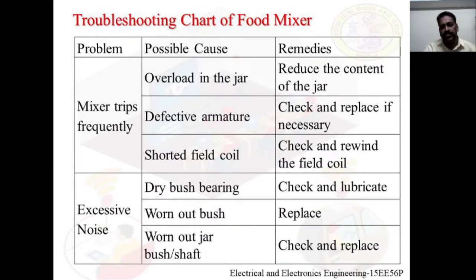The next problem is mixer trips frequently. The main reason for this is overload in the jar. Reduce the content if necessary. Defective armature. So this is also one of the reasons for frequent tripping. Check the armature and replace if necessary. Shorted field coil. Check the winding and rewind if necessary.